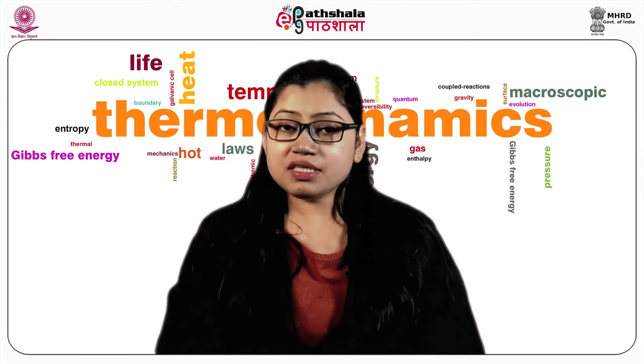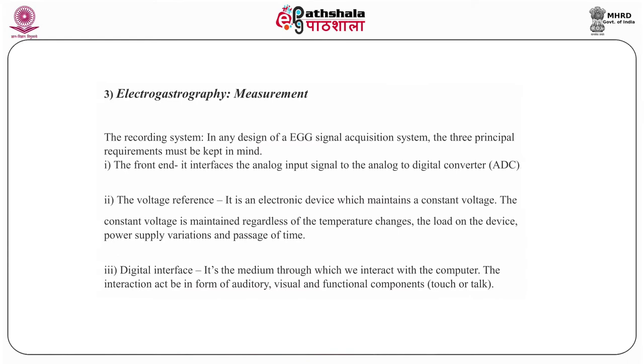Now we are going to talk about the measurements of electrogastrography — the recording system. In any design of an electrogastrography signal acquisition system, three principal requirements must be kept in mind. First is the front end, which interfaces the analog input signal to the analog-to-digital converter (ADC). The second is the voltage reference — an electronic device which maintains a constant voltage regardless of temperature changes, load on the device, power supply variations, and passage of time.